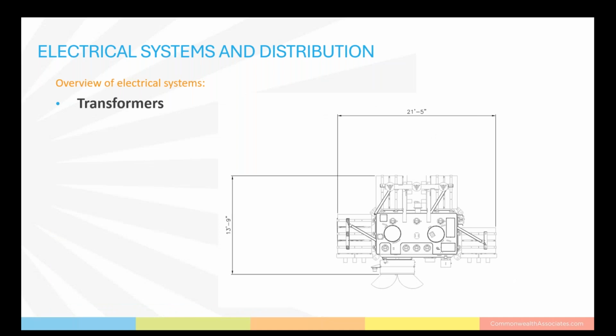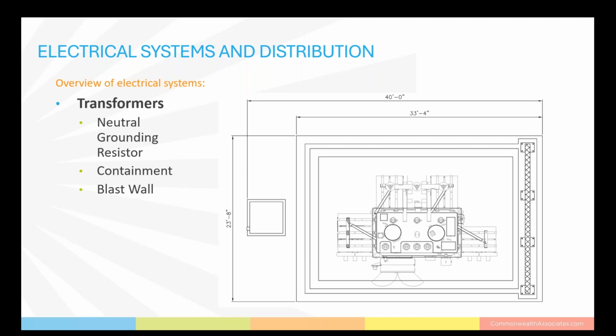This is a plan view of the transformer from the 3D model you saw on the previous slide. You can see that the overall size is fairly large at almost 14 feet by 21 feet. But when you take into consideration my comments from the previous slide in regard to blast wall and containment, we need more space. As you can see, when we add the blast wall and containment foundation, plus any other ancillary equipment, for example, the neutral grounding resistor shown to the left, we end up with space requirements that jump from 14 by 21 feet to an overall space of 24 by 40 feet.